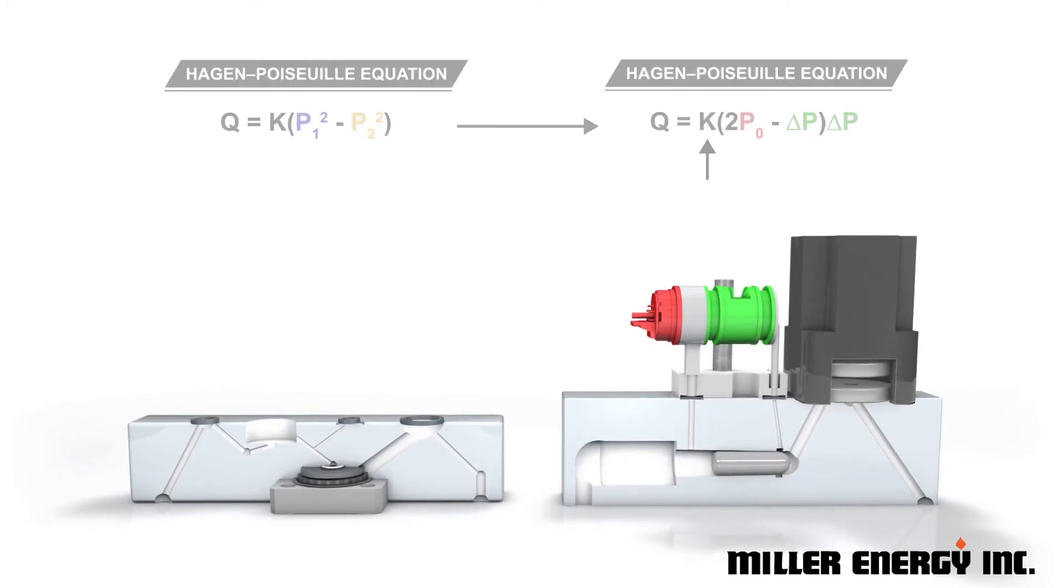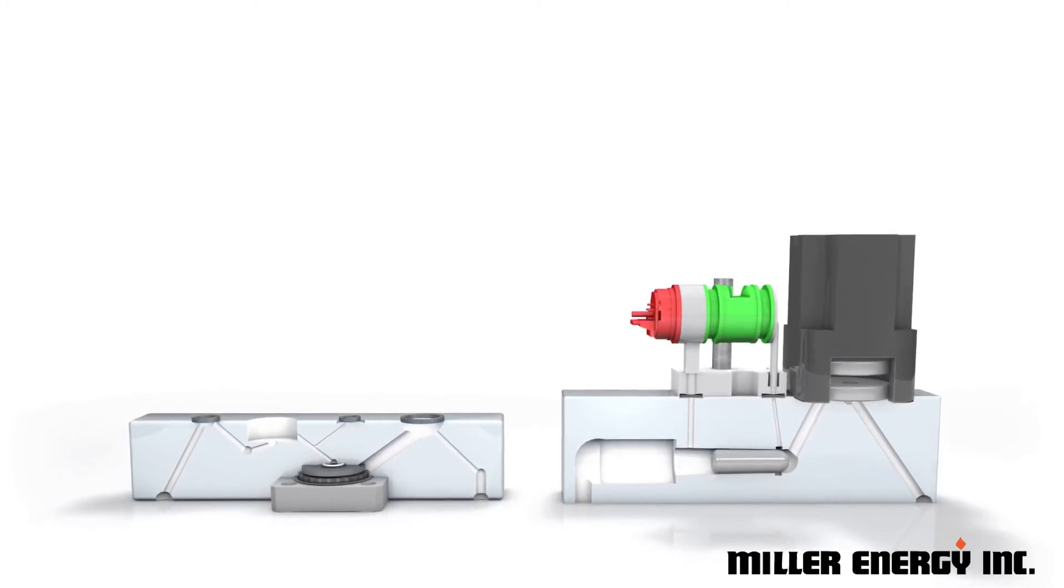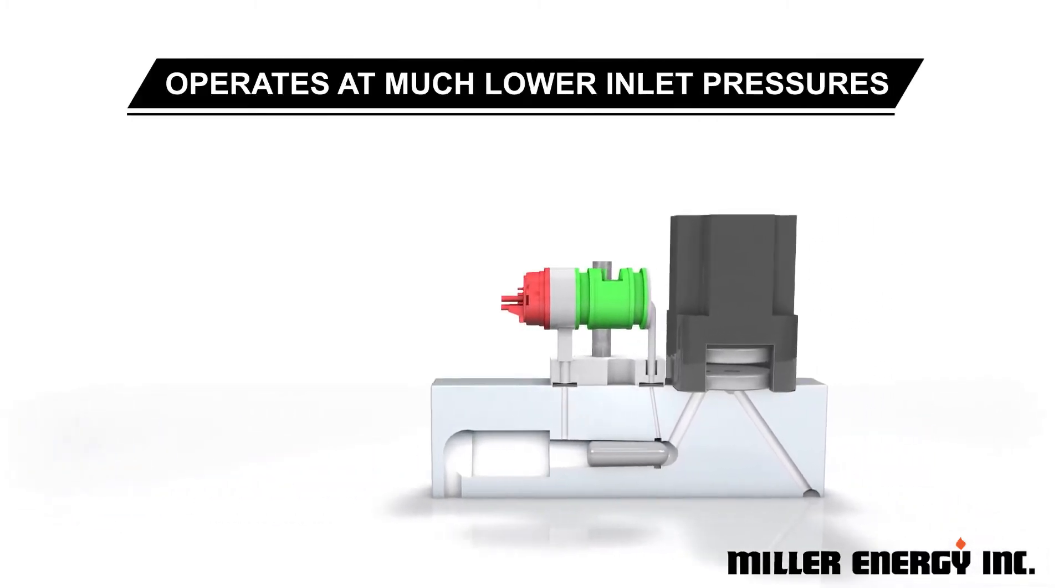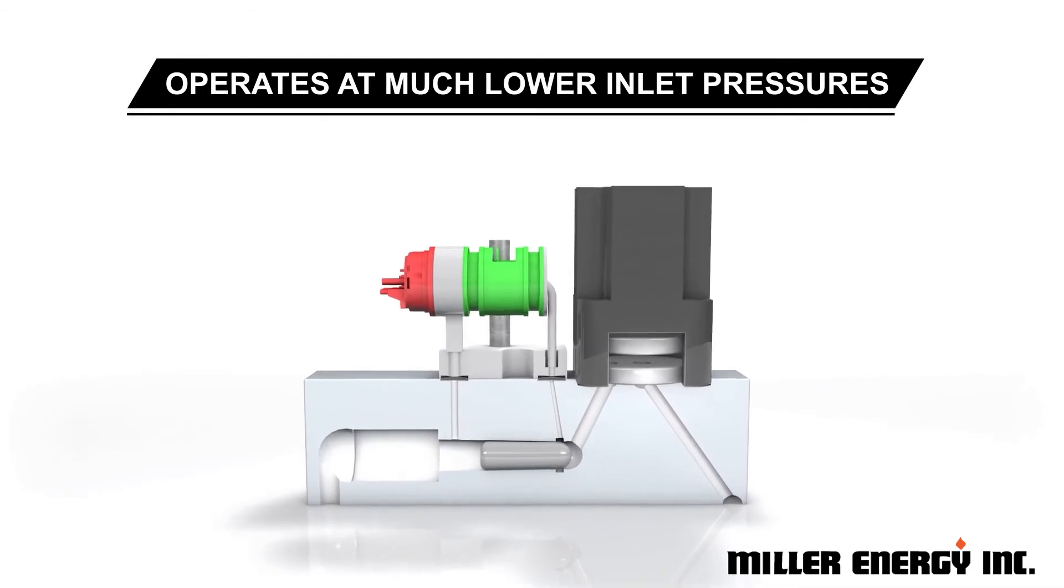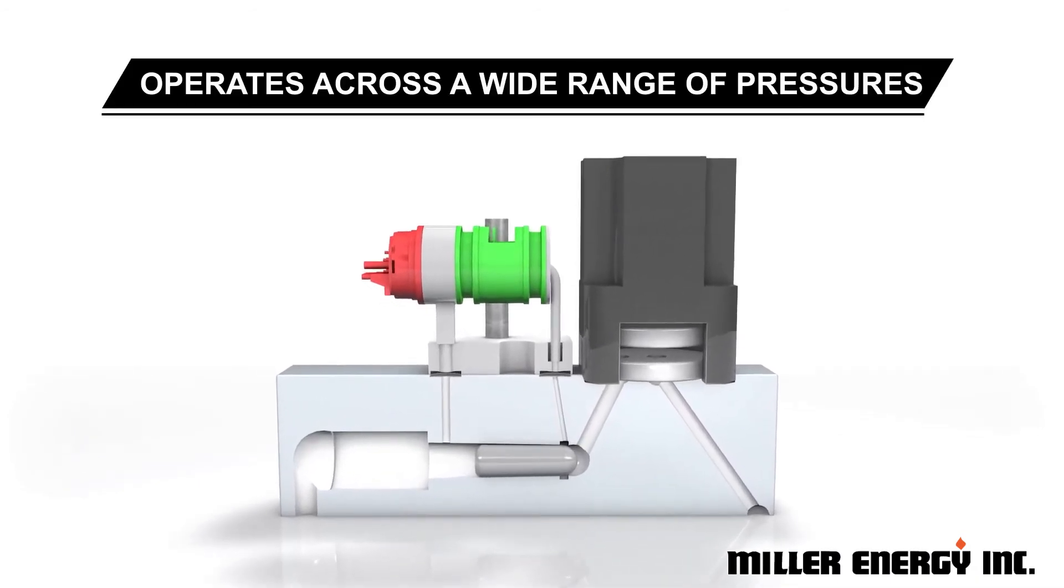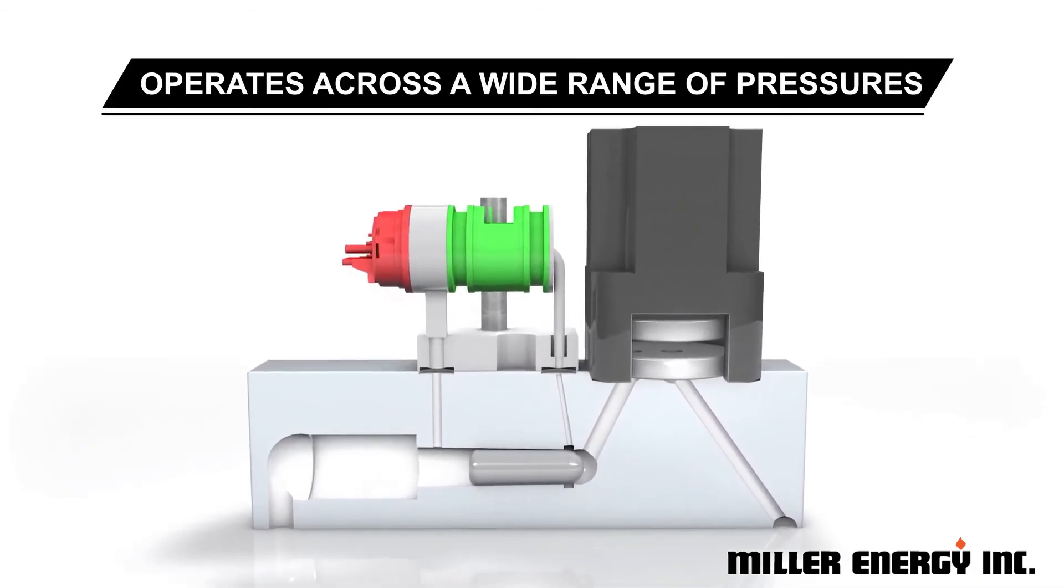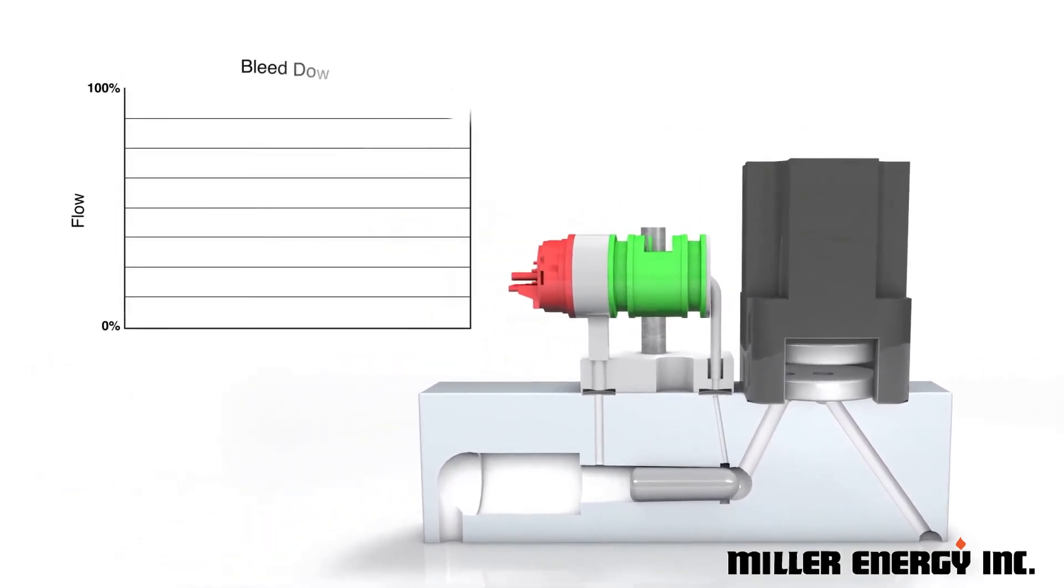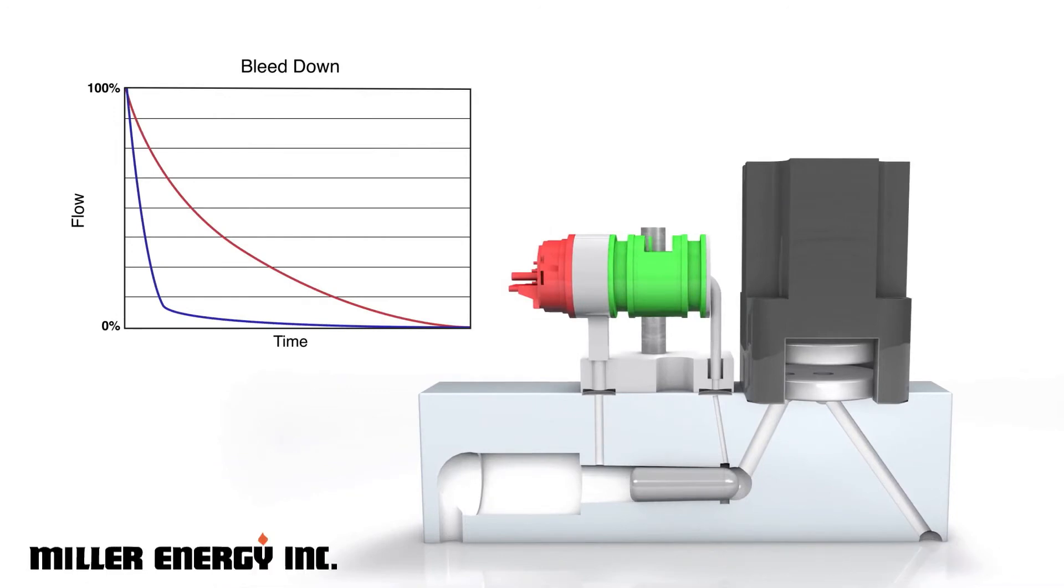Combined with the downstream valve architecture, this enables the GP200 to operate at much lower inlet pressures and across a wider range than other pressure-based MFCs. The downstream valve also removes the bleed-down effect and ensures the device is insensitive to dynamic outlet conditions.